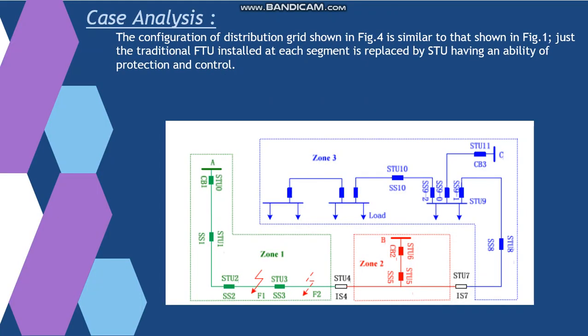It also consists of three zones A, B and C. For example, if a fault F1 occurs during the open loop. STU0, STU1 and STU2 will detect a fault current after the fault has occurred. Because IS4 is opened, STU3 cannot detect the fault current and the other remaining STUs will also see normal current. So STU0 will communicate with STU1 and STU1 will again communicate with STU2. Hence the mode of communication is downstream.